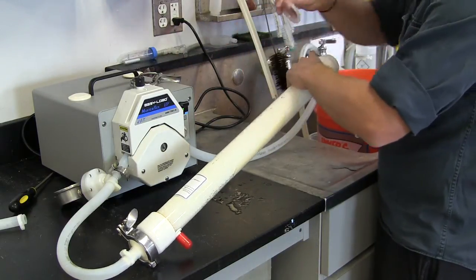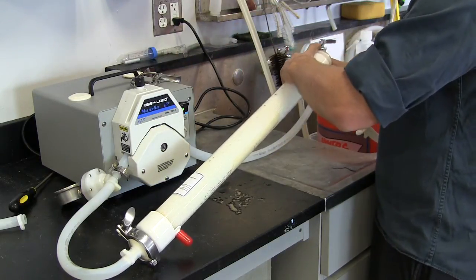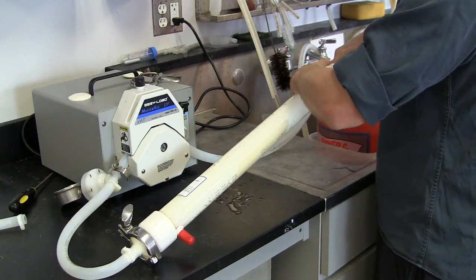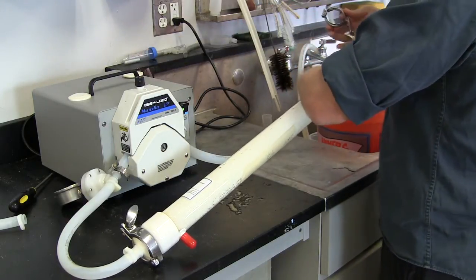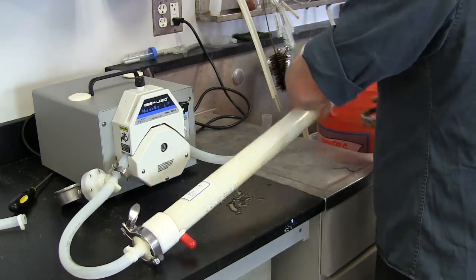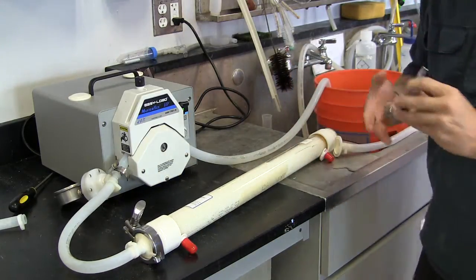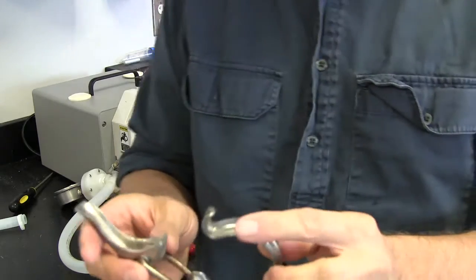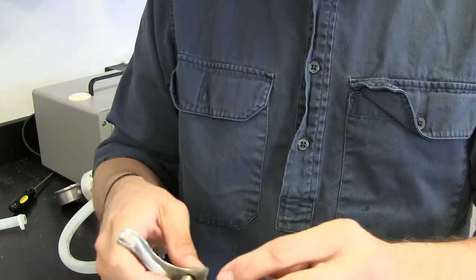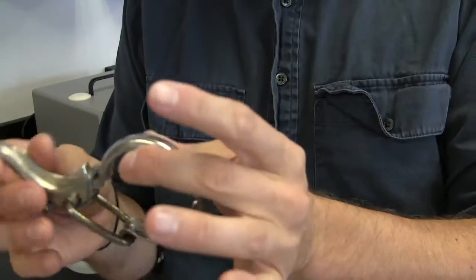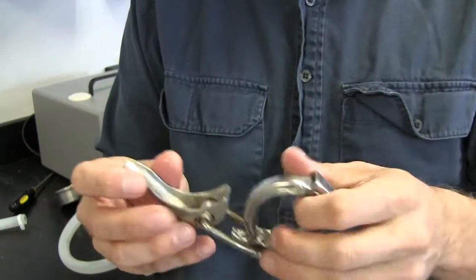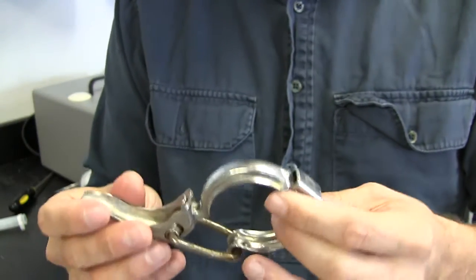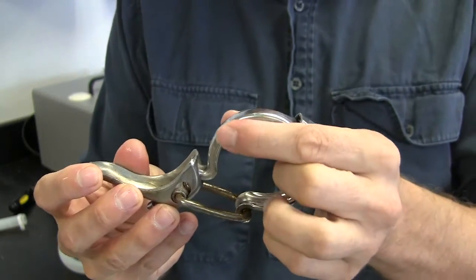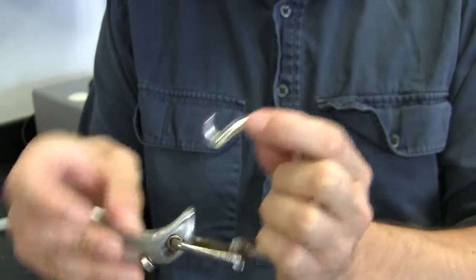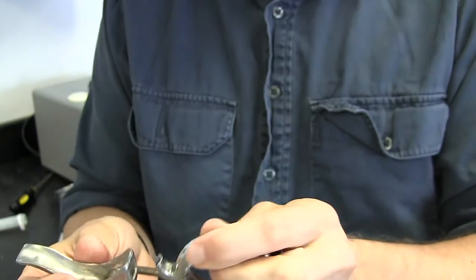Alright, once again, placing the clear rubber ring back on here, attaching the cap again, and then reattaching this clamp. Oh, I should point out this particular clamp. This clamp is a very common type of clamp on our TFFs. It loops in like so, so you'll take it off and it will look like this. All you do to open it is you pull this little tab out from the lever part. Then to redo it, you clip that back in and clamp it down.